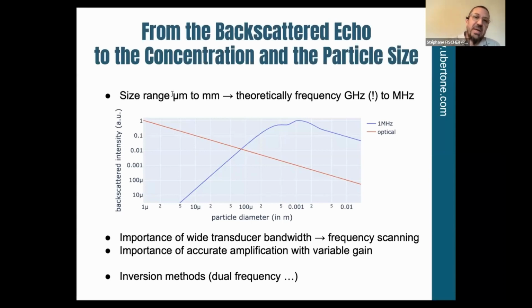So ideally, for particles from the micron to the millimeter, we would need frequencies from the gigahertz to the megahertz. Unfortunately, for acoustics, it's not possible to reach the gigahertz value, but at least we can work from the megahertz to a few tens of megahertz. Having said this, it's important to have the possibility of different emitting frequencies in order to have access to the different particle sizes. Also, the bandwidth of the transducers allows a better frequency scanning, which is why having a wideband transducer is quite important. Also, due to the huge variation of the echo intensity as a function of the distance, it's important to have accurate amplification with a variable gain.